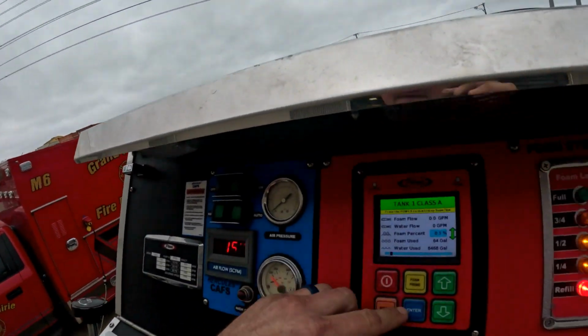All right, so we got all our foam put back into the tank. We'll let it sit here for a while, come back, just double check it for leaks. So far so good. I'm really excited about that. Okay, so normally I would recalibrate the LVDT transducer. We're just gonna go in here and check. We're gonna check the percentages, and check the voltages.